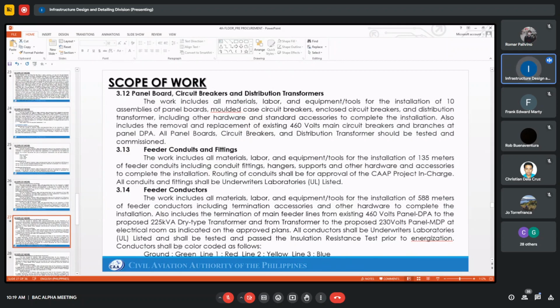Feeder conduits and fittings includes all materials, labor, and equipment for the installation of 135 meters of feeder conduits, including conduit fittings, hangers, supports, and other hardware and accessories to complete the installation. Routing of conduits shall be approved by the CAAP project in charge. All conduits and fittings shall be UL listed.